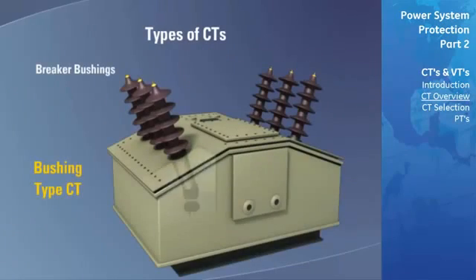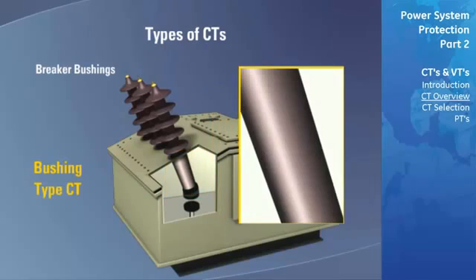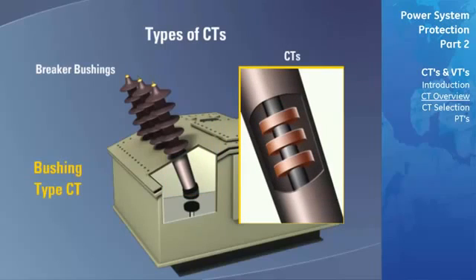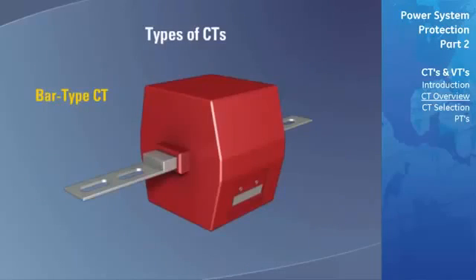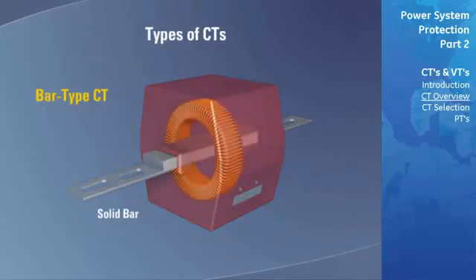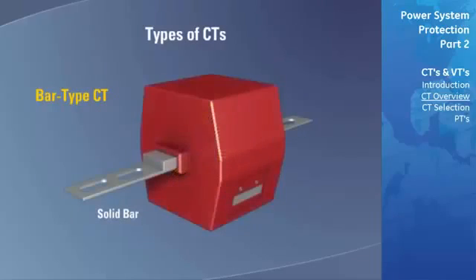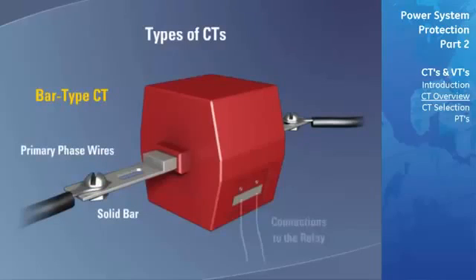A bushing-type CT refers to a CT that is built into another power system device, such as a breaker. Terminals are provided on these devices to permit connecting the CT to a relay. A bar-type CT has a solid bar that passes through the annular core to form the primary winding of the CT. The primary phase wires of the power system are then connected directly to these bars to complete the connections.